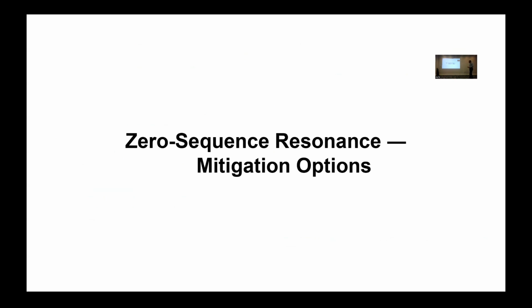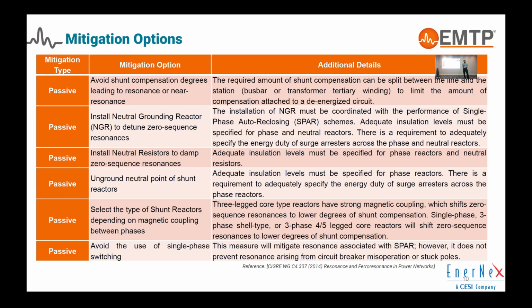Well, so there's an issue, and there are mitigation options available as well. Mainly they are classified into two categories: passive actions and active actions. If we look at the passive options, one would be to avoid the shunt compensation degree. It basically means resizing the shunt reactor such that there is no resonance condition, or dividing the compensation between the line and then substation.